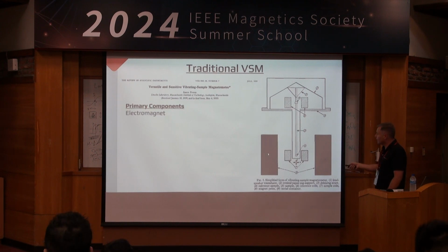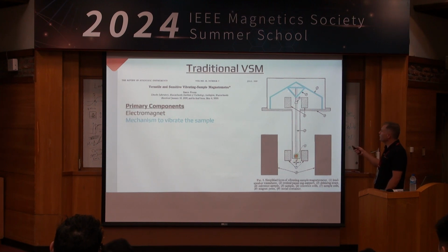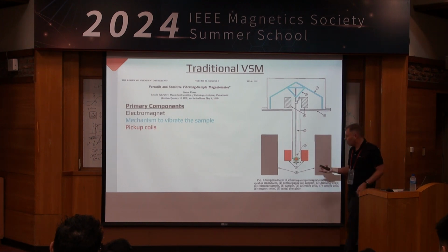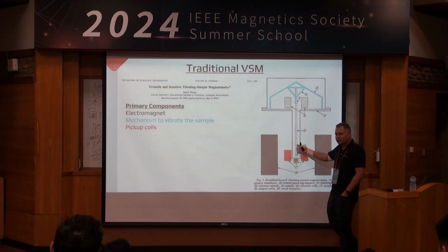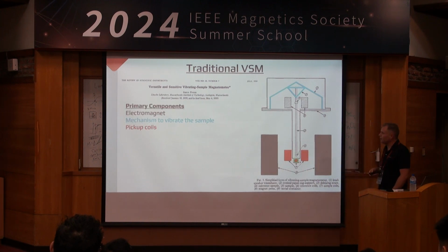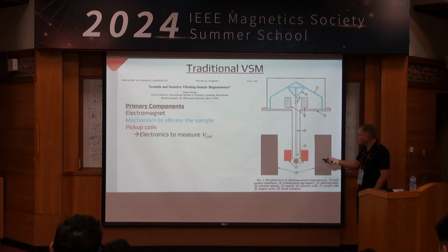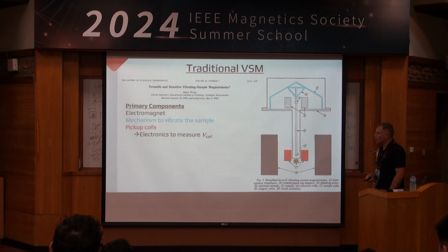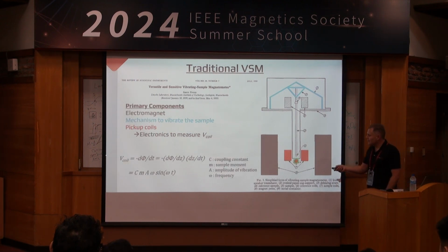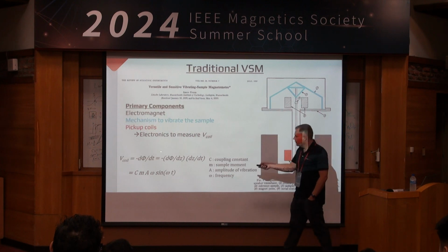Primary components are an electromagnet, a mechanism to vibrate a sample, usually a speaker coil could be used, and pickup coils in the vicinity of the sample to inductively pick up the dB/dt variations in the field in this vicinity here. We need some electronics to measure the voltage induced in this coil, usually a lock-in or something similar to that. And basically, this is our equation for this system here.